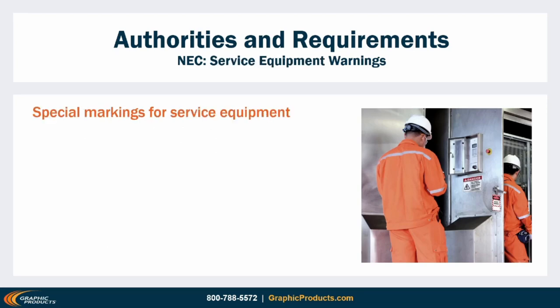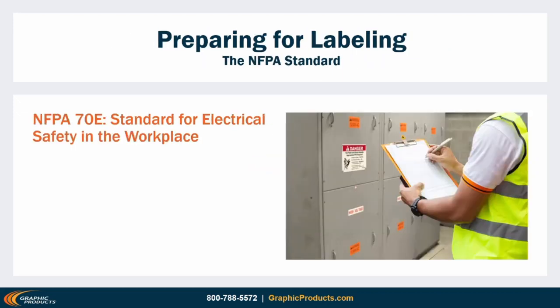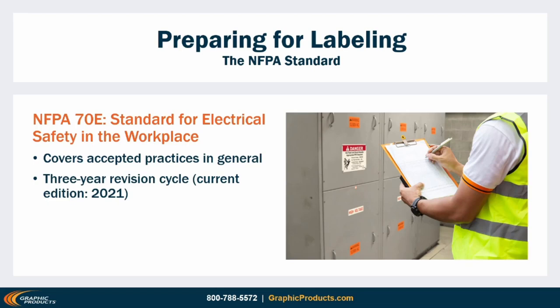Requirement B only covers service equipment rated for 1200 amps or more, and requires more specific details. These signs need to identify nominal system voltage, available fault current at the protective device, clearing time for that device based on that current, and the date of the label. However, this label is not required at all if the equipment has a dedicated arc flash label that follows accepted industry practice. You can find these accepted practices in NFPA 70E, which describes accepted practices for workplace electrical safety based on expert opinions and industry consensus, updated every three years, most recently for 2021.